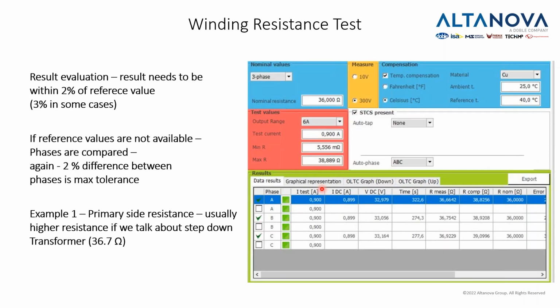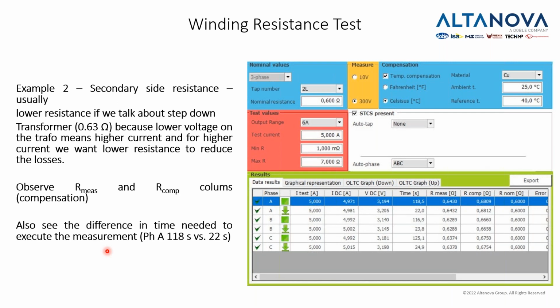Here are some results. When we measure, of course, we measure on the primary and the secondary side, all positions of tap changer, all phases. In this case, we see quite high resistance on the primary side because the primary side has lower current, it can have a higher resistance, 36.7 ohm, while in our next case, we can see that the resistance is much smaller, 0.63 ohm. So this is like 70 times smaller, almost.